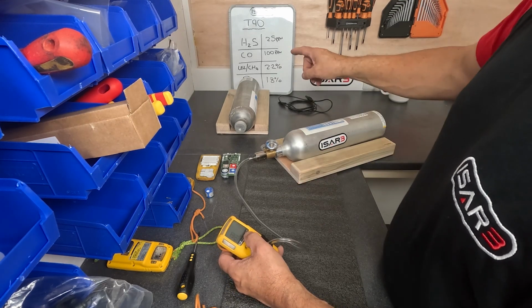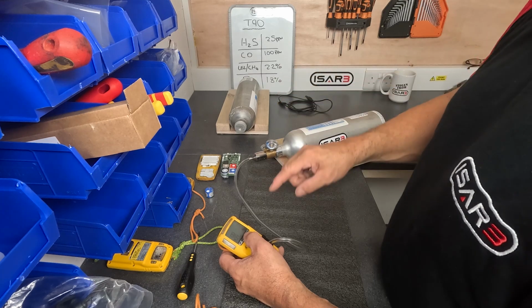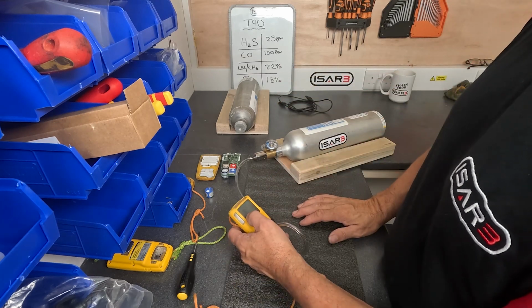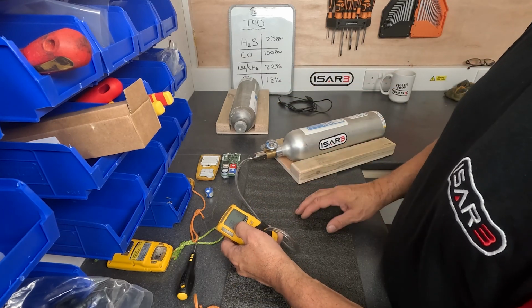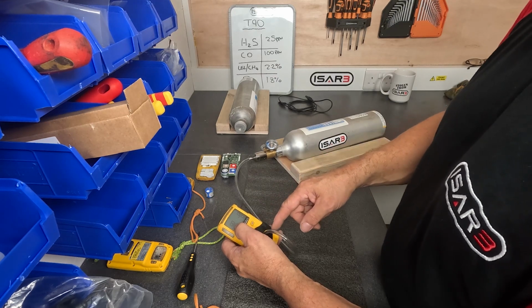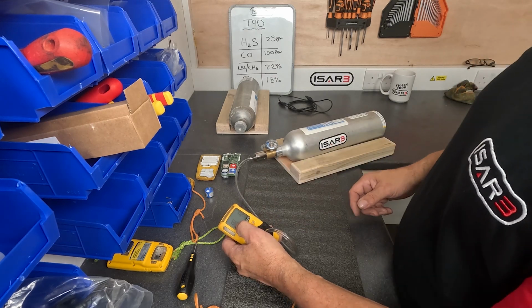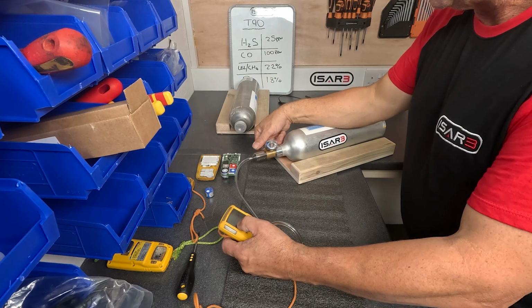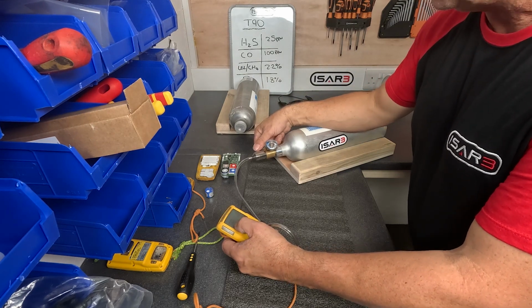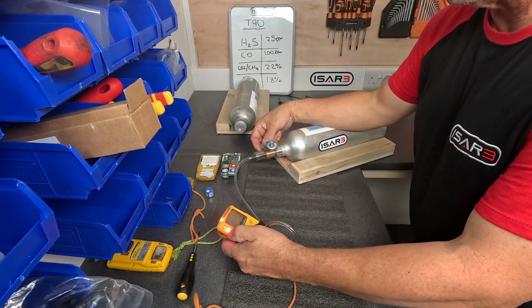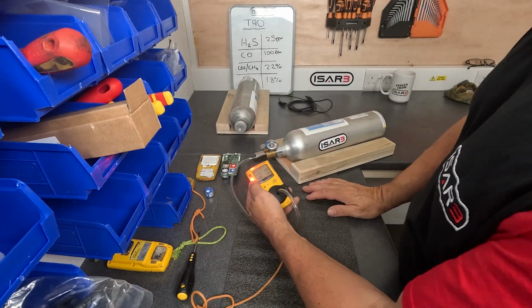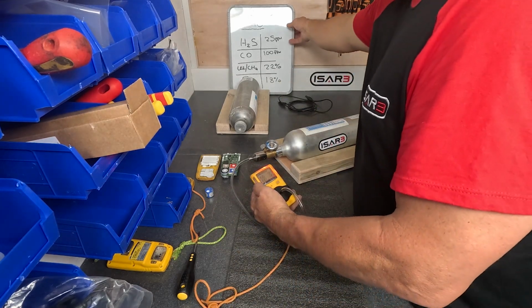By looking at these numbers and seeing how long it takes for the gas detector to stabilize to these numbers, we can get a sense of how clean the filter is and how healthy the sensors are themselves. But we'll just go ahead and do one. So I'm going to turn the gas on, and you can see almost immediately the gas detector starts to react.